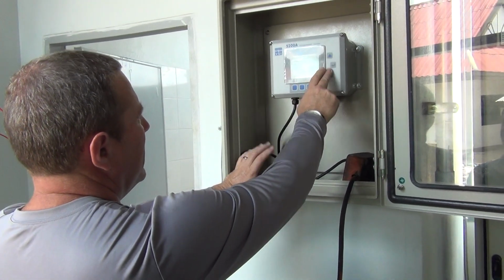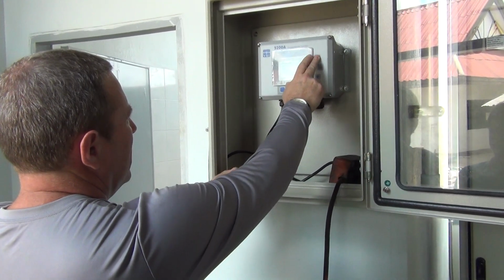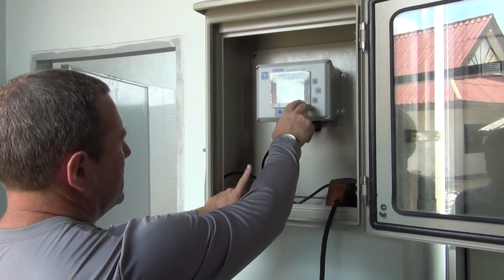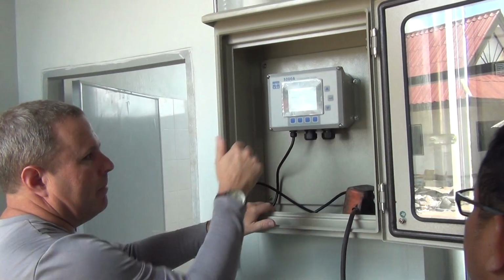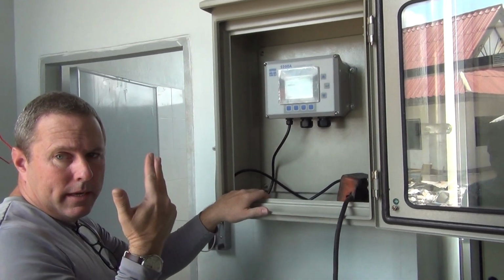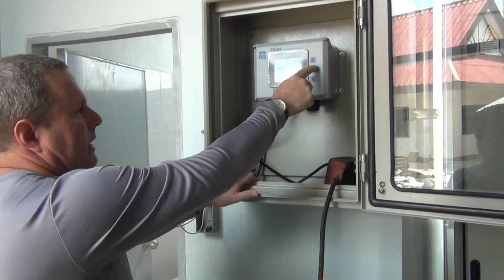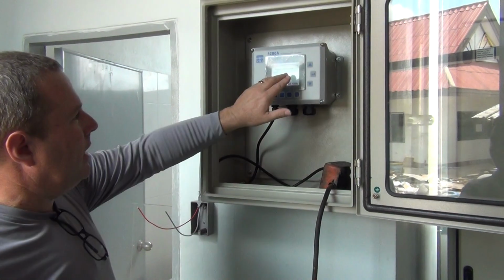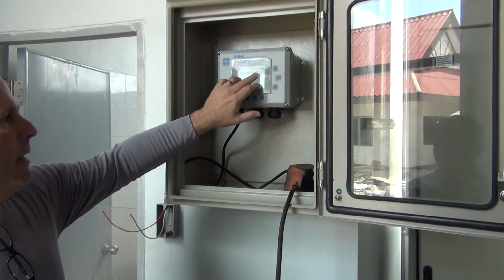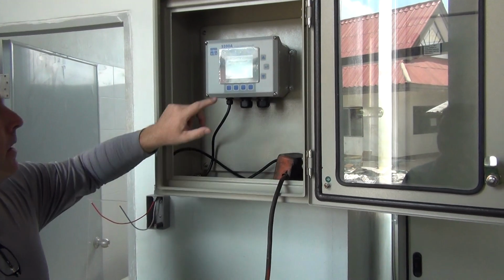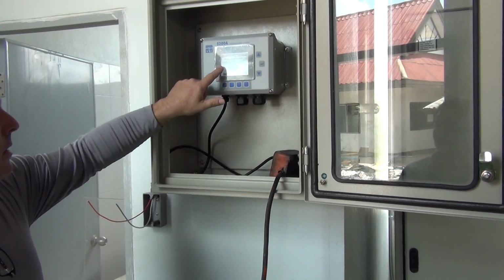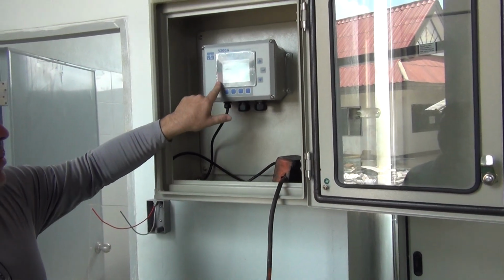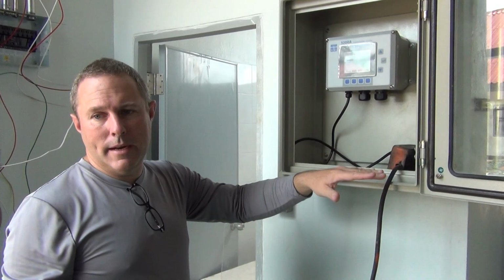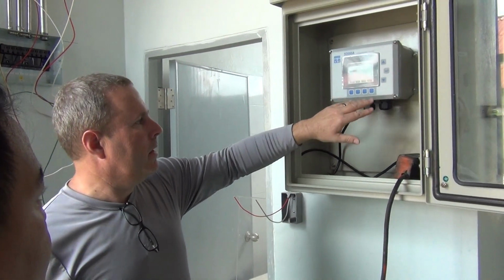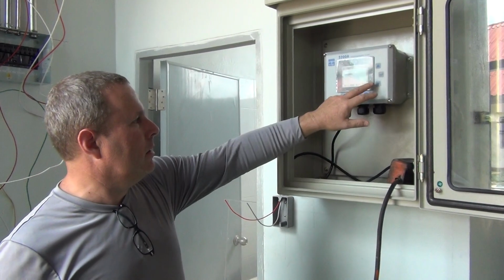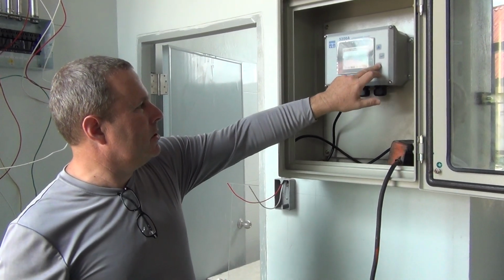Sorry, we need to first set up the network, my apologies, and the data logging. So we do that first. So the data logging is under menu, system, data logging. So I see data logging, I press enter. It says data logging enabled. It samples every 1 hour. Event logging enabled. And then the last option is if we, for one reason or another, wanted to clear all the data logs. This would manually clear them. So it is enabled for 1 hour.